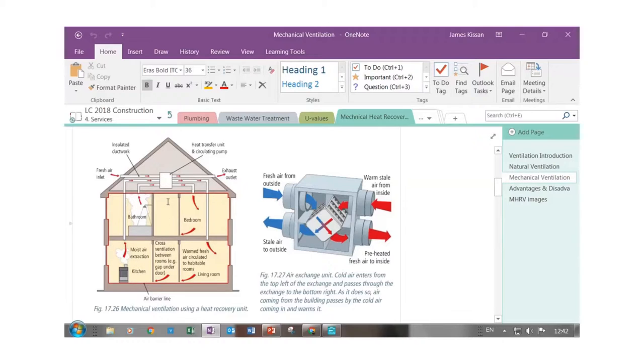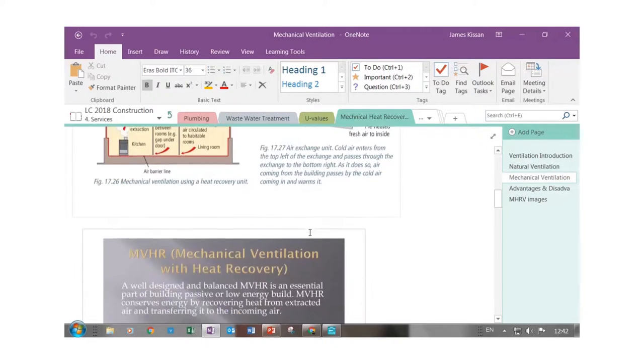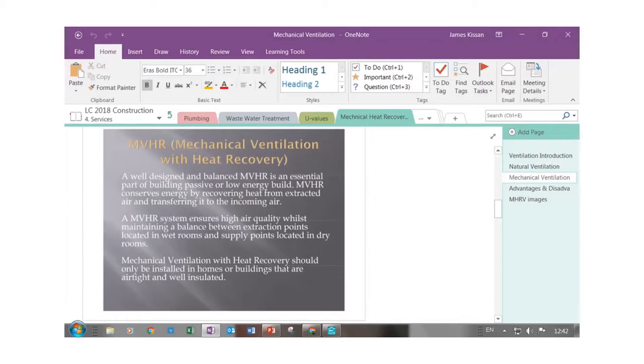Because air is being taken out of one room it has to be replaced from somewhere else — for example, from the living room. So warm fresh air is pulled around the house. This system will only ever work in an airtight house — it will not work in a house that is not airtight, because gaps in the building fabric mean heat and air escaping. So MVHR has to be used in conjunction with an airtight house.